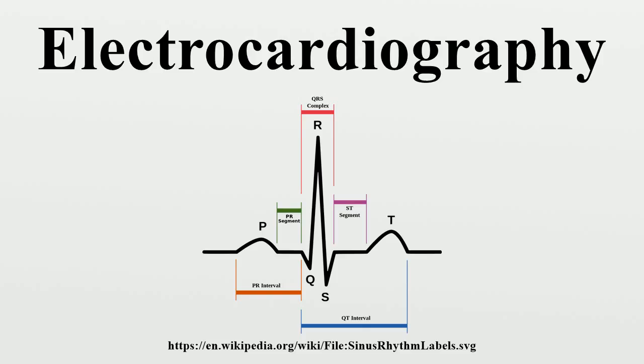Ten electrodes are used for a 12-lead ECG. The electrodes usually consist of a conducting gel embedded in the middle of a self-adhesive pad. The most common type of electrodes for ECG application is silver/silver chloride. The term lead in electrocardiography refers to the 12 different vectors along which the heart's depolarization is measured and recorded.